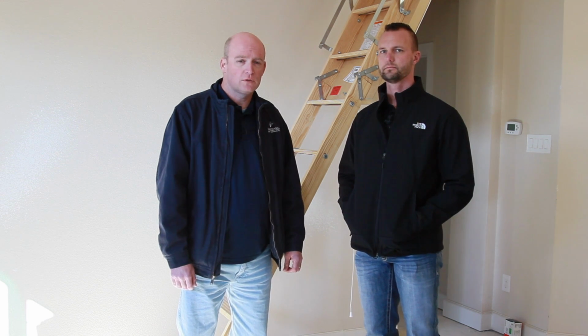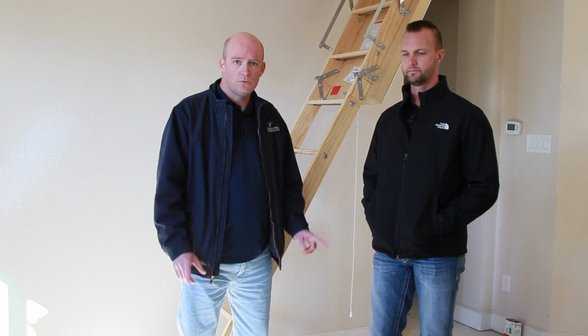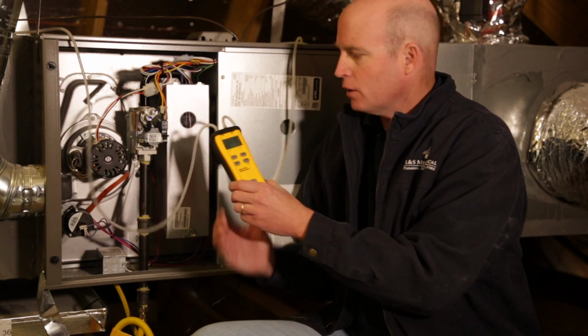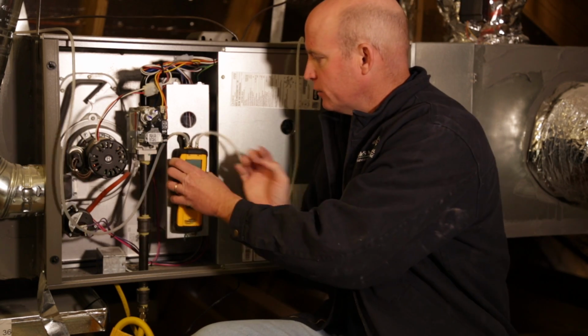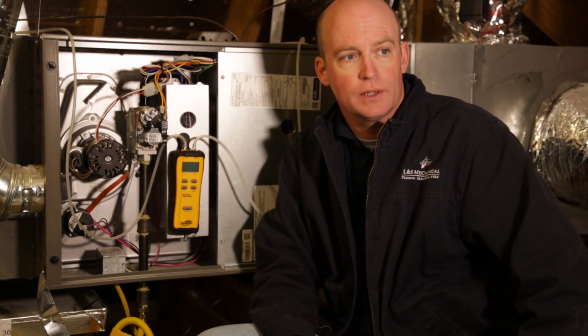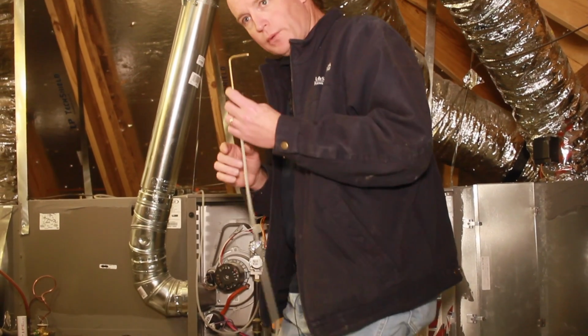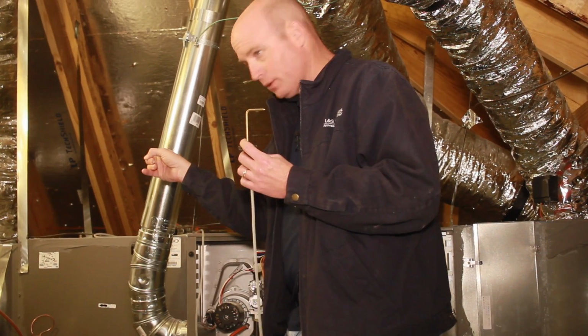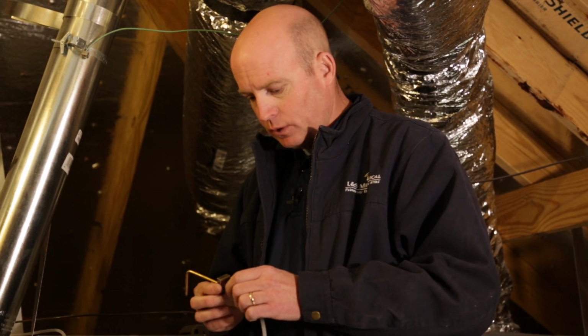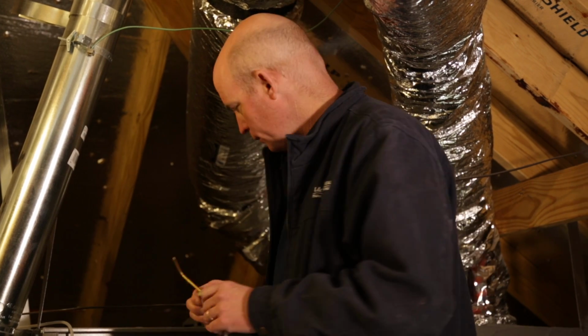So the next thing we're going to do is transition into the attic, and we'll show you test points to take external static pressure, and we'll also talk about two other locations where we take static pressure measurements. Well, now we're in the attic with the equipment that we're going to test. So what we're going to do is talk about our meter and where to place the static pressure tap hole locations. And we have our probes. We have one here, and we have one over here. We're going to drill two holes. Now, I've cheated, and we've pre-drilled these holes, but I'm going to pick up the drill and show you where we would place them.